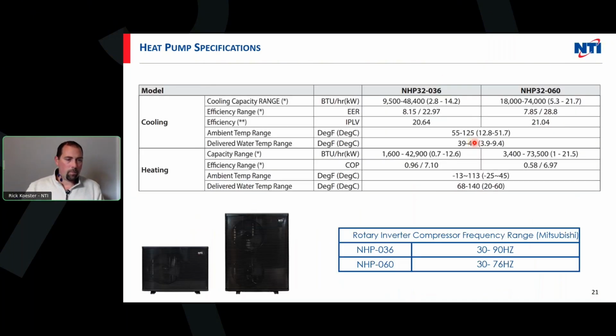Performance range on the cooling capacity, anywhere from 9,500 to 48,000 plus on the 3-ton, up to 74,000 on the 5-ton. Heating capacity up to 42.9, about 43,000 BTUs on the 3-ton, and 73.5 on the 5-ton. You can see the frequency range here. This being an inverter piece of equipment, it can ramp up and ramp down from 30 to 90 hertz on the 3-ton and 30 to 76 on the 5-ton. So we can reduce our capacity because of inverter heat pumps now.